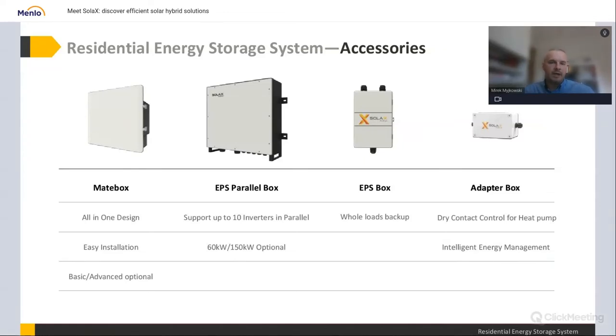So first, as I said before, the meter has to be on the border between the house and the grid. So if that border between the house and the grid is in that matebox, you have to bring the power to all the house first to the matebox, and then you can go back. And if the whole power comes into the matebox and just passes through the switching device, then the whole house will have emergency power supply as well.